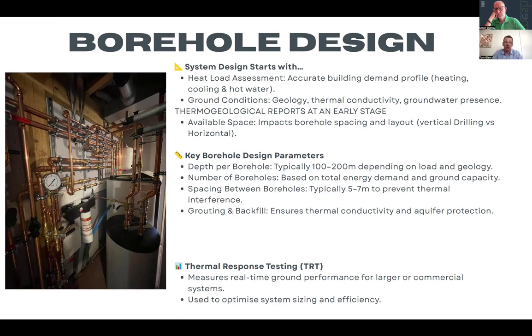Because you can design the boreholes and they will perform really well for the first two or three years, but they will over extract, and then in the following years the efficiency will drop and drop. So, let's say, extraction rates from 30 watts per meter will drop down to 28, 25, and it will carry on dropping.